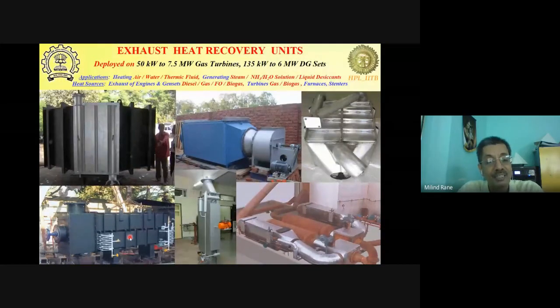Okay, now this is another unit. These were modular. So here we have deployed two modules, and there was a sonic soot blower and soot blowing using steam. Both options were there, or compressed air. And then this is another unit which we deployed on a 7.5 megawatt gas turbine. Our size was 1/3 the size which otherwise the international consultant had allocated for this based on the conventional design. This was used for heating thermic fluid from 230 degrees to 250 degrees centigrade using exhaust from a gas turbine. Now, exhaust from a gas turbine is typically extremely clean, so there were no issues about fouling in this particular case. Another example of a clean exhaust heat recovery was a micro gas turbine of 50 kilowatt. This entire unit was fabricated in a lab.